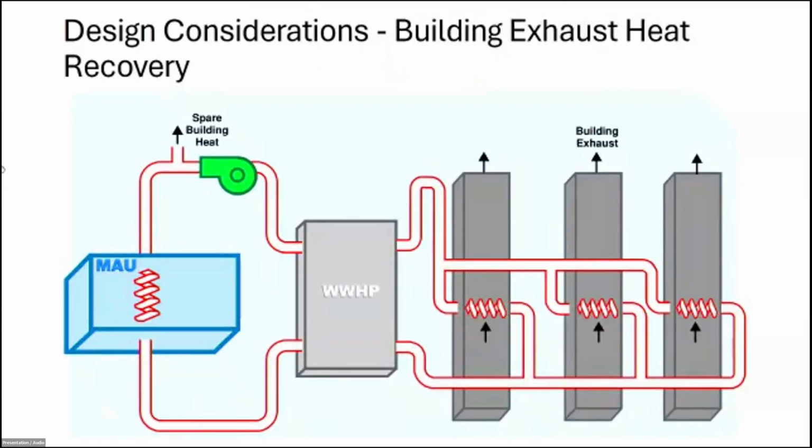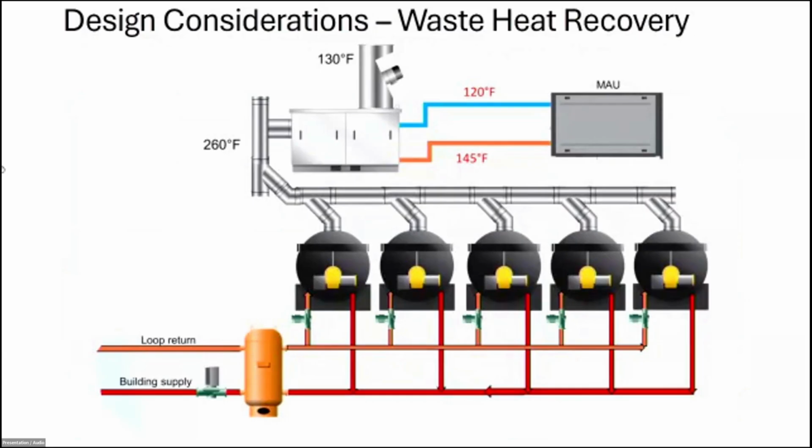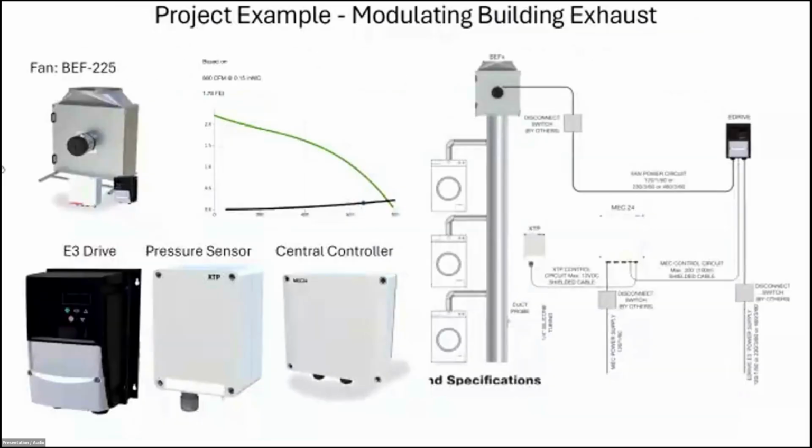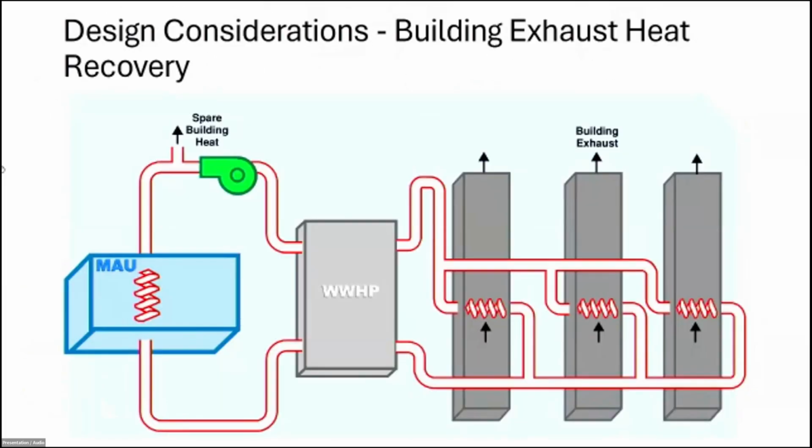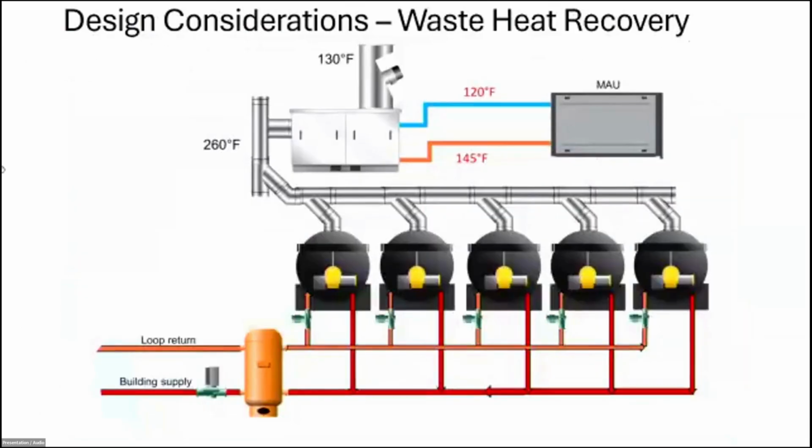So, very complicated, great project, very expensive. This is much, much simpler. And this gets them all the way that they need to go. This gets them that 70 degrees of lift. This gets them waste heat recovery incentives and rebates available from the programs that exist, and is just a really, really good, solid way to do the system. This system is already tapping out. So on those coldest days, this system is running as hard as it can. And right now, under this last design, that makeup air unit just can't get there. This gets them all the way there.